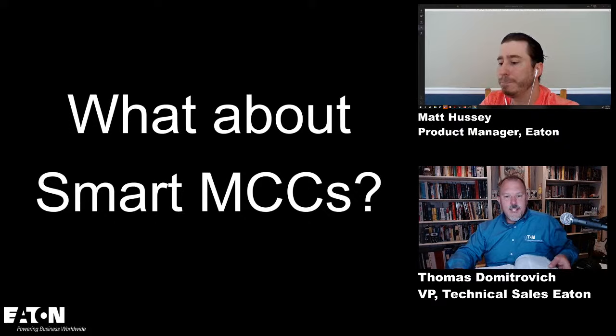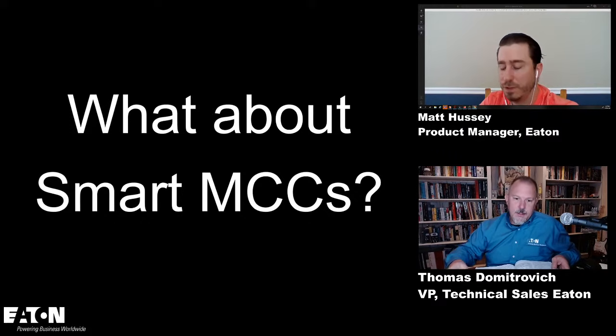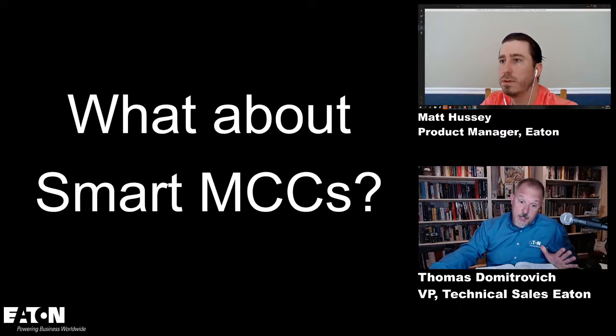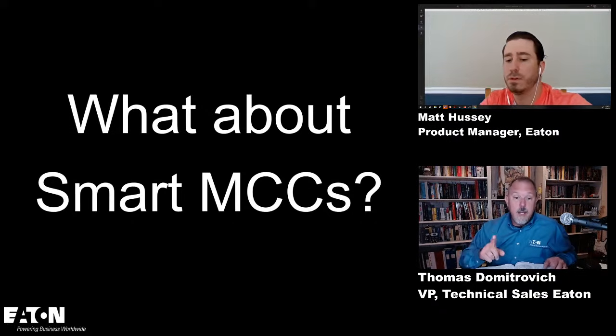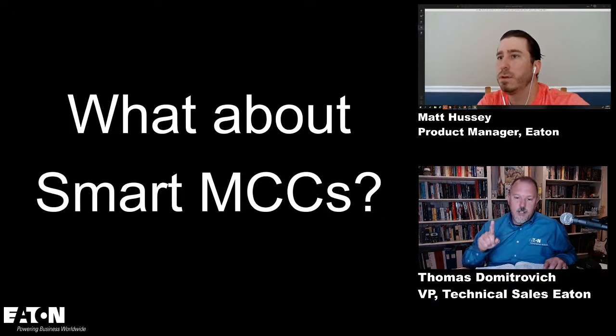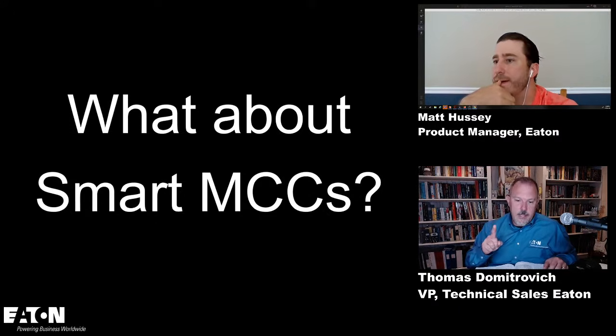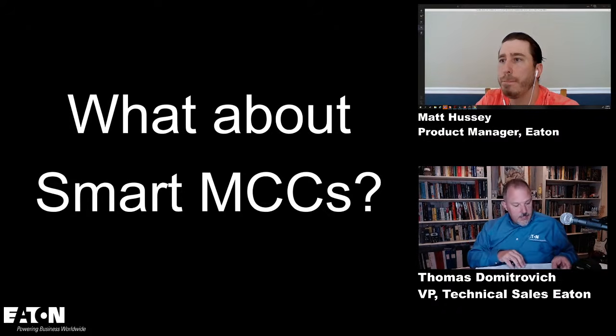Excellent. And I just popped over to Facebook, and there's a gentleman out there, with UL, great guy, and 24 minutes ago and 14 minutes ago, he posted a couple cool things. On the question of a fire pump controller in the MCC, he says look at 695.12(A). 695.12(A) says electric motor-driven fire pump controllers and power transfer switches shall be located as close as practical to and within sight of the motors that they control.